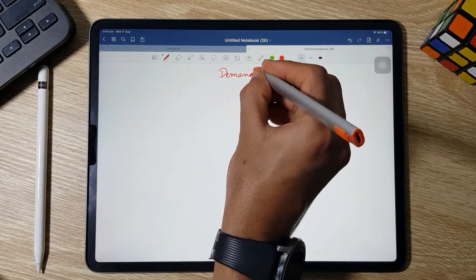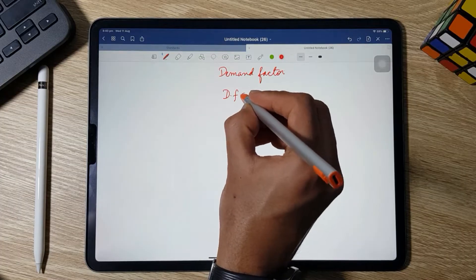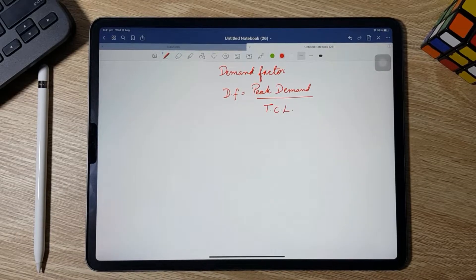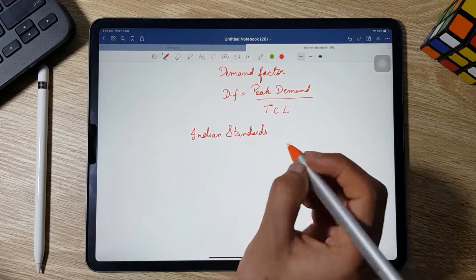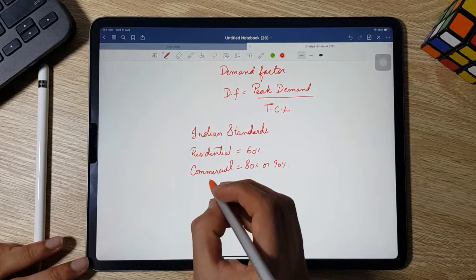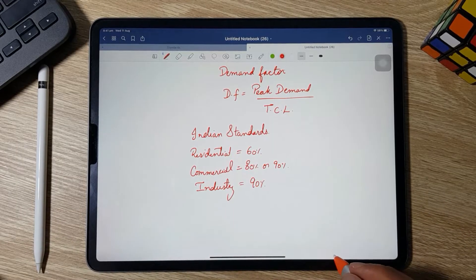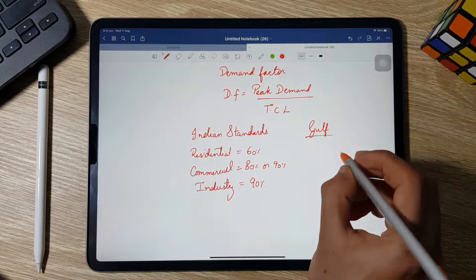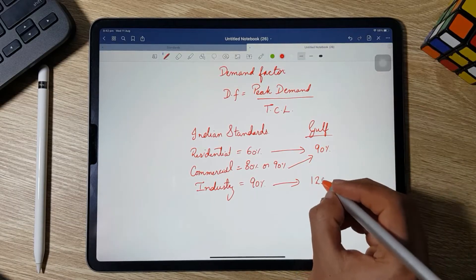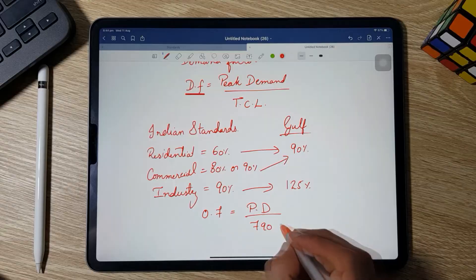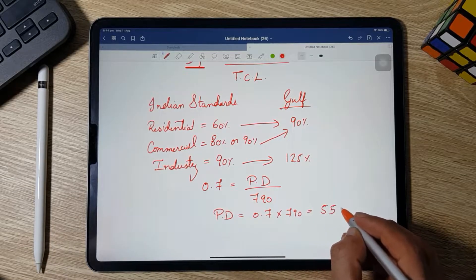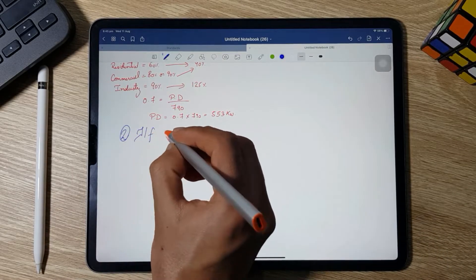Before moving to Step 2, we need to calculate peak demand using the demand factor formula: peak demand = demand factor × total connected load. According to Indian standards, the demand factor is 60% for residential and 80–90% for commercial; in Gulf countries it is 90% for residential and 125% for industrial. Here we are considering 70%, so peak demand = 0.7 × 790 = 553 kW.